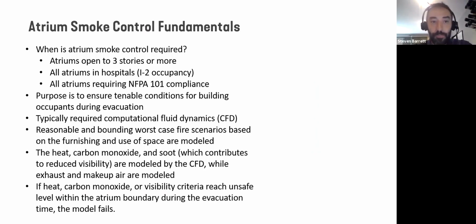So when is atrium smoke control required? In atriums that are open to 3 stories or more, an atrium smoke control system is required by code. If you are working on a hospital project, an I2 occupancy, all atriums require smoke control. If you're working on an NFPA 101 project, that's often adopted by government, federal, or a local jurisdiction, then all atriums require smoke control. And the purpose of the system is to ensure tenable conditions for building occupants during evacuation.